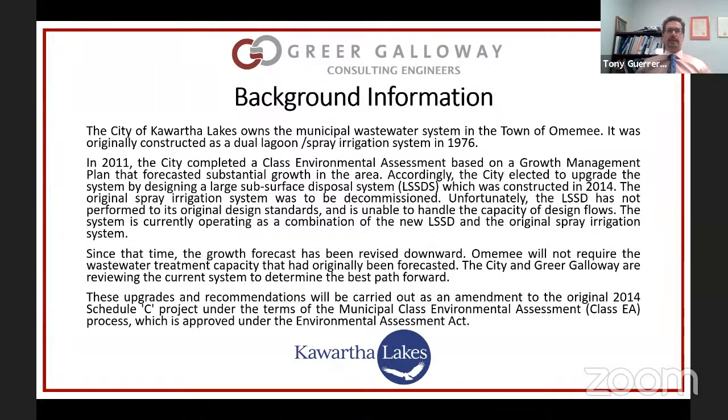The Omemee Wastewater Treatment System was installed in approximately 1976 and it consists of two lagoons as well as a spray irrigation system. Wastewater enters the lagoons and it's stored over the winter period, and in the summer it's sprayed — it's called spray irrigation. It's fairly commonly used: you basically spray the effluent out onto licensed fields and some of it evaporates and some of it percolates down into the ground. In this case, spray irrigation is used rather than discharge to surface water.